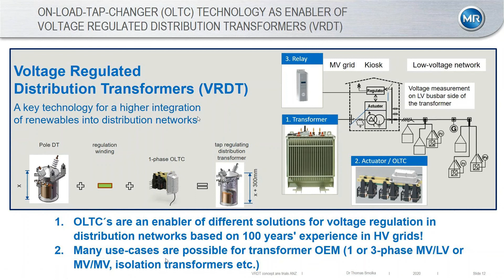I mentioned a couple of examples: single phase SWER applications, three-phase MV-LV distribution transformers, or an MV-MV regulator, or also, as you'll see from another trial or rollout going on in Victoria with PowerCor as part of their RevCal project, they have also used a tap changer for regulating the isolation transformers they're using there.